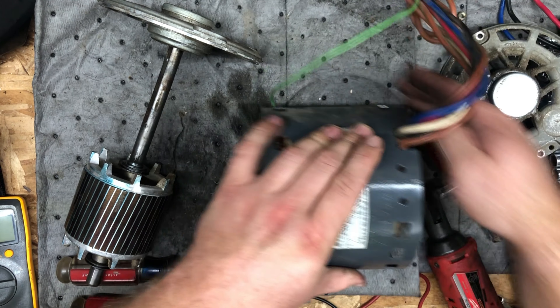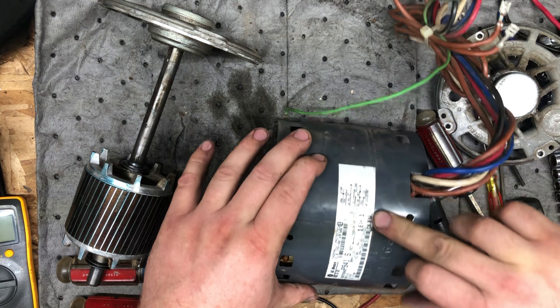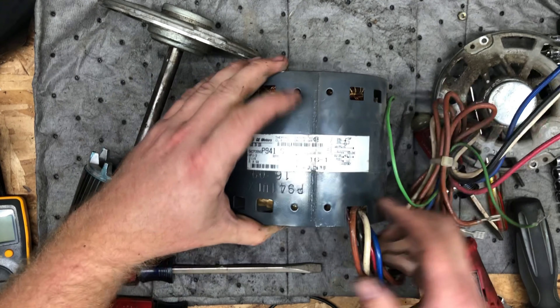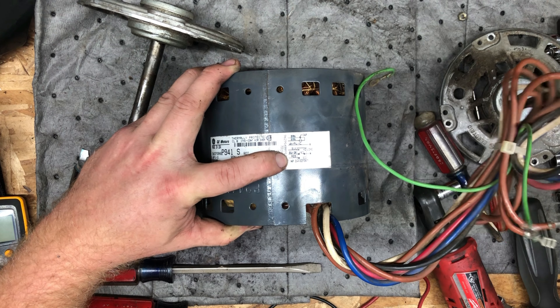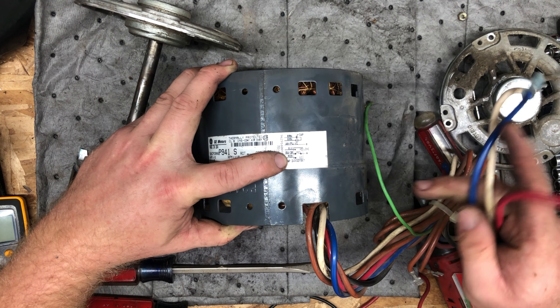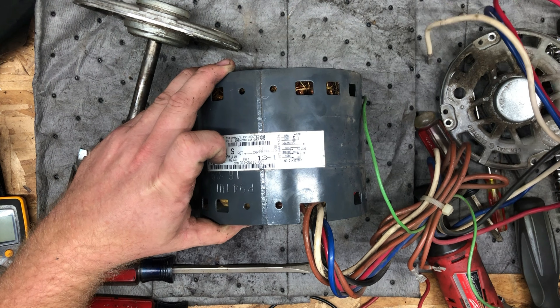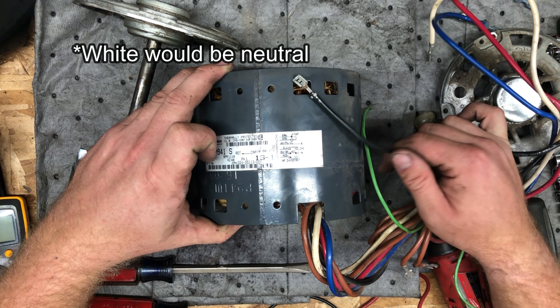Here's what I was talking about before — here's the little wiring diagram. Brown to brown is the capacitor. Black is high, blue is medium, and red is low. So those would be your three speed leads. And then the white or the remaining lead would be your ground or your return line.